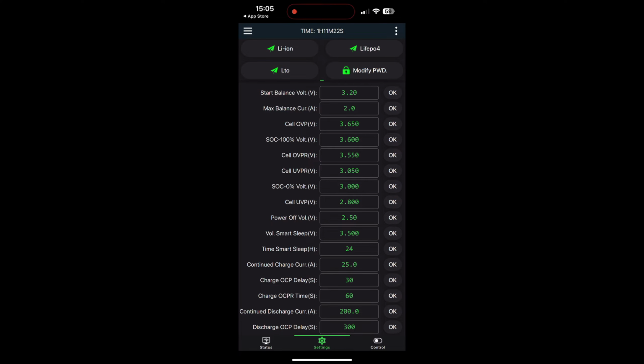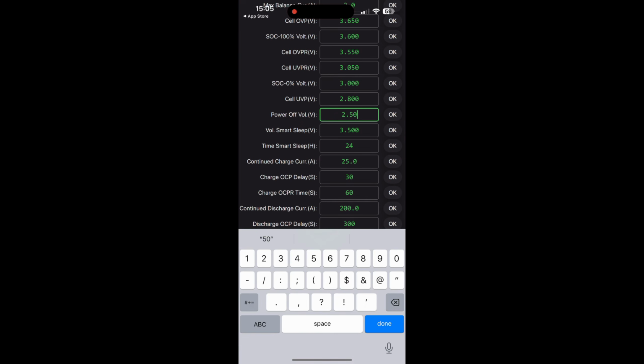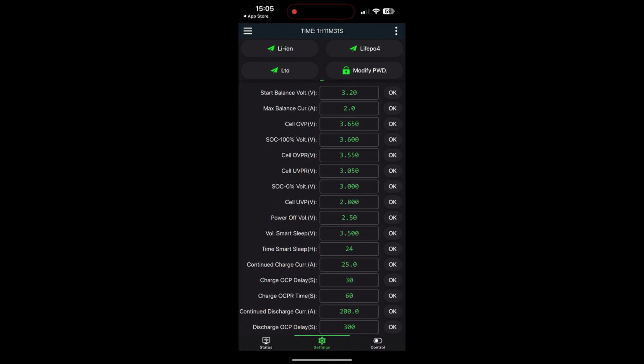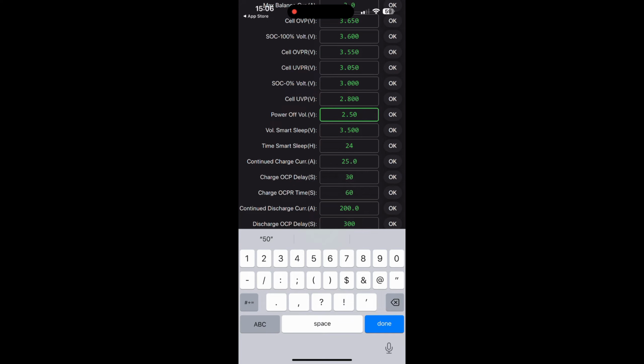Below the cell UVP, which is under voltage protect, there's power off. Now, this power off is at what point do you want the BMS to actually be disconnected totally? Now, in this battery, what will typically happen is it'll come down and hit, in the settings we've got, 3 volts, and it'll be at 0% of usable capacity, but for the total capacity, we're saying it's 2.8. You could put that to 2.5 if you want to. But once it stops allowing any charge to come out of the bank, the BMS will still be active. Now, the BMS requires power to run, okay? So the BMS will still draw current out of the battery in order to be active or be on. However, if we go to the power off and we put that to 2.5, it will stay alive until the power off hits 2.5 volts.